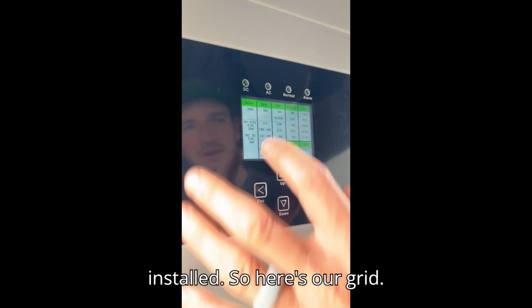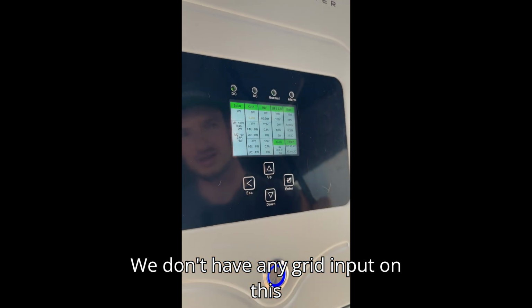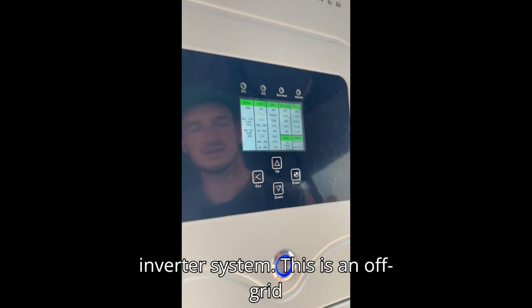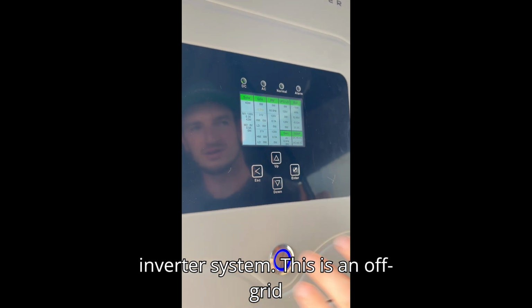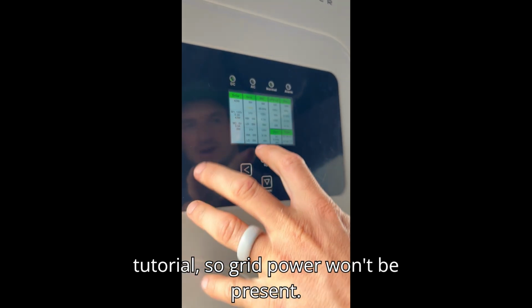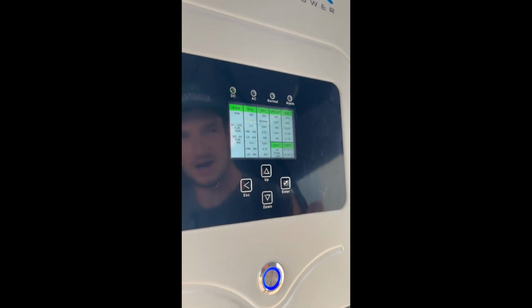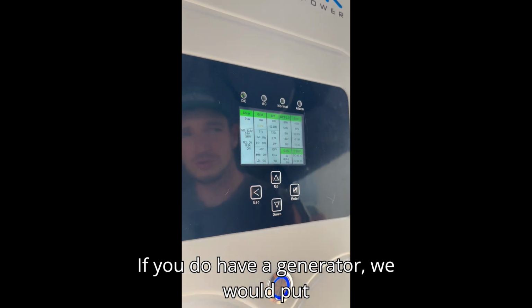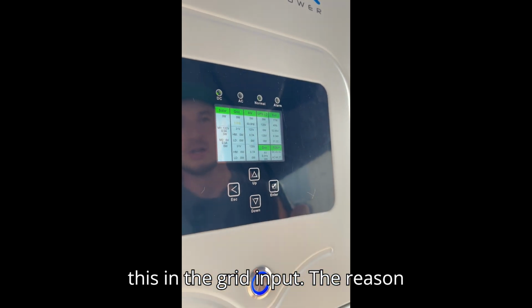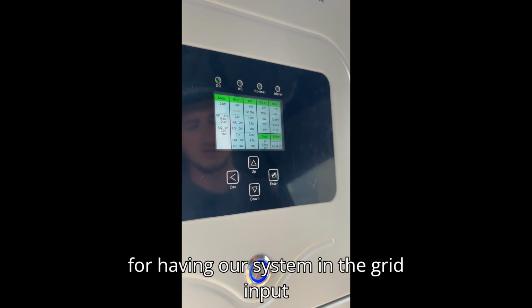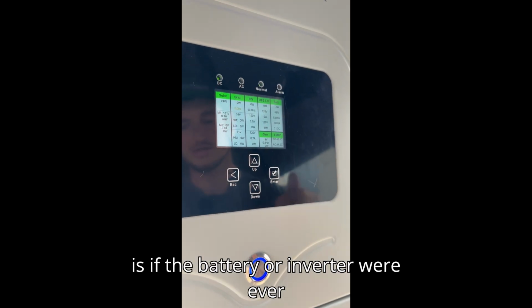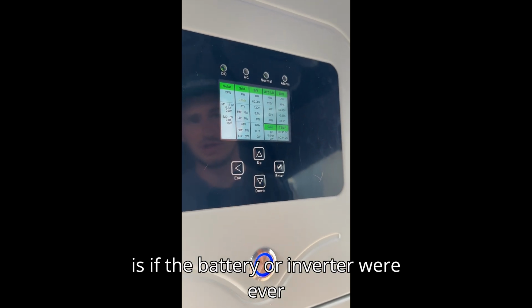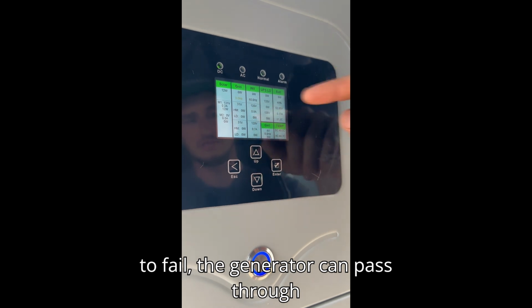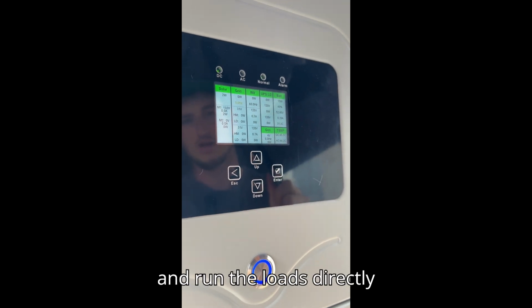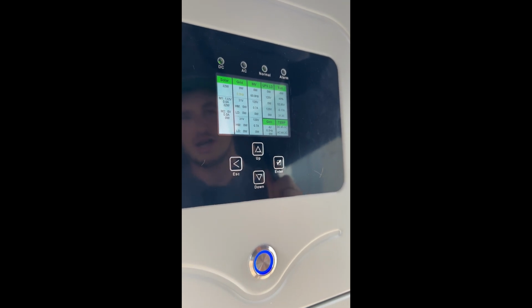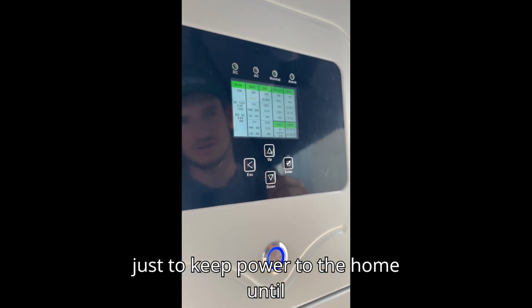Here's our grid. We don't have any grid input on this inverter system. This is an off-grid tutorial, so grid power won't be present. If you do have a generator, we would put this in the grid input. The reason for having our system in the grid input is if the battery or inverter were ever to fail, the generator can pass through and run the loads directly, just to keep power to the home until we're able to service it.